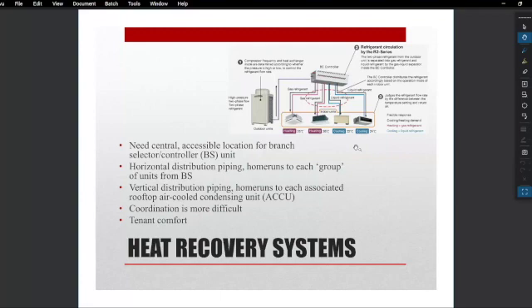All right, with the heat recovery, the only difference for us is we're adding a branch controller that has to be centrally located so that it can distribute to an apartment. Generally, that's how we do a home run to each apartment. All of those home runs can be isolated, and one apartment can be heating while another apartment can be cooling. And you could even go further and do home runs to each individual fan coil unit. But that really brings in a lot of horizontal piping and really complicates coordination. And in general, in an apartment, you're either going to be in heating or cooling.